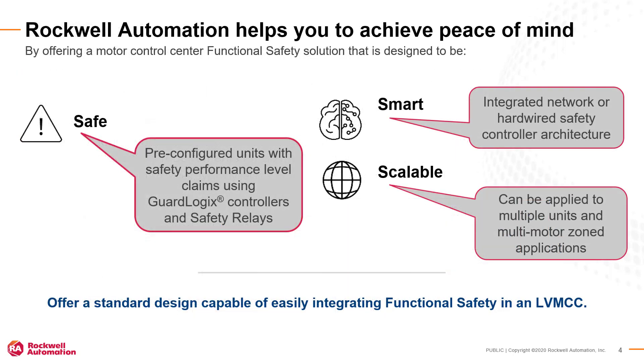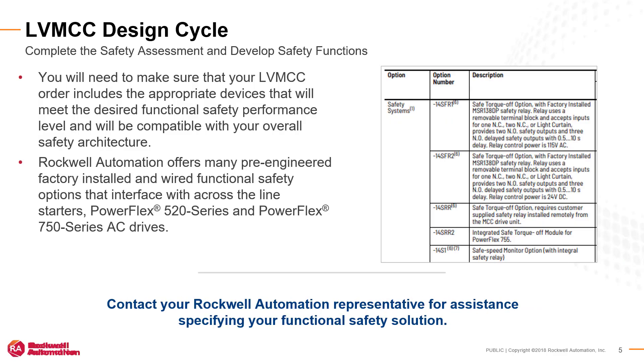Centerline Low Voltage MCC units have documented functional safety performance claim levels with either hardwired or GuardLogix safety architectures. Functional safety can be applied to single motors, multiple units, and multi-motor applications that are grouped in specific safety zones. You will need to make sure that your MCC includes the appropriate devices that will be compatible with your overall safety architecture and will meet the desired performance level.